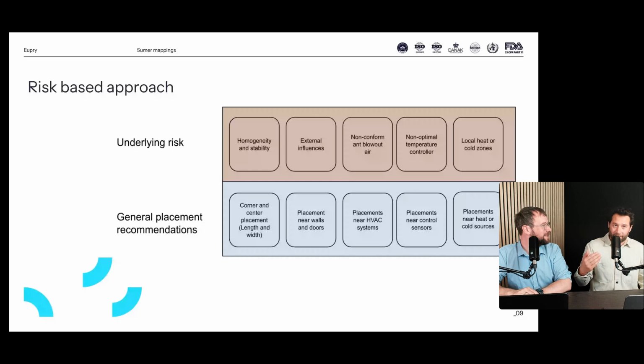So, underlying risk. Continuing with the risk-based approach, we have the underlying risk, and here it is necessary to understand it, because it's the homogeneity and the stability of the unit itself. That's why having more measuring points, for example, and understanding to some extent how thermodynamics works in a space is very important, because not every space is as homogeneous or stable as you might think. Just think about when the compressor kicks in and the air vent starts blowing cold air in a specific area, then you have one specific point that is way colder than the rest of the room.